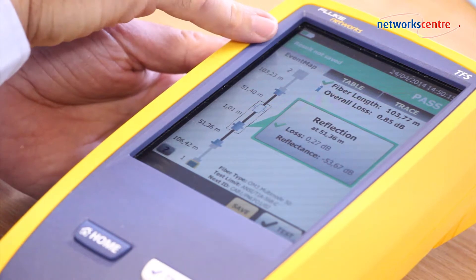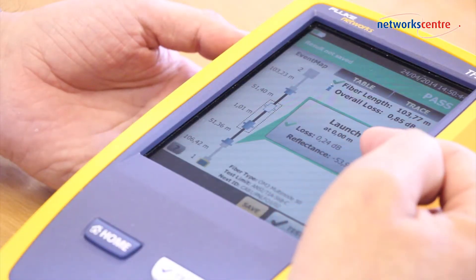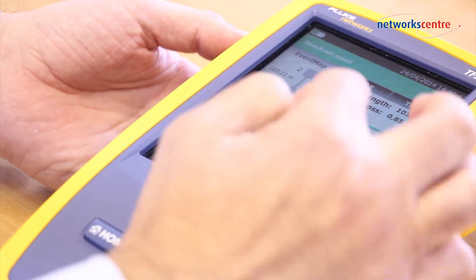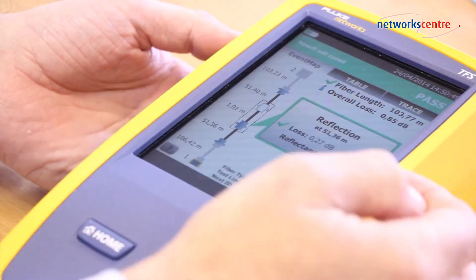What we can see now is the unique EventMap, which gives a pictorial display of the information usually apparent on the trace to an OTDR expert. It gives the loss and the reflectance at each particular distance, and moving along to the next event does exactly the same. We can clearly see a one-meter patch cord indicated within our link.